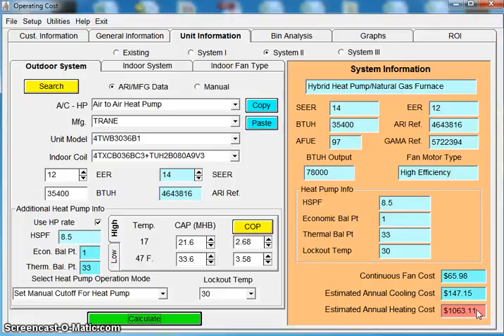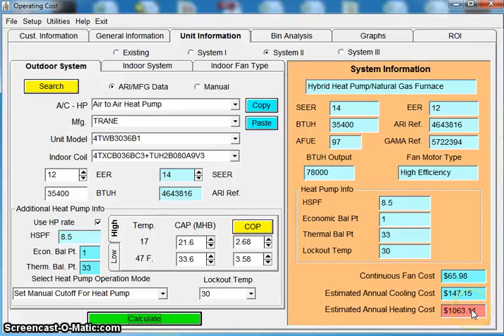And you'll see my heating cost drop by another four or five hundred bucks just by going with the heat pump. So in these two comparisons, we've compared a 13 SEER air conditioner to a 13 SEER heat pump. The furnace is the exact same. That heat pump is saving us another 500 bucks a year, which will be really powerful when we get into return on investment.